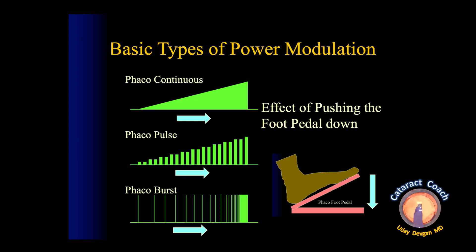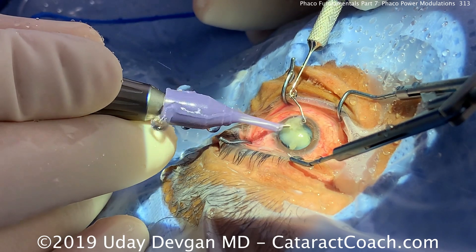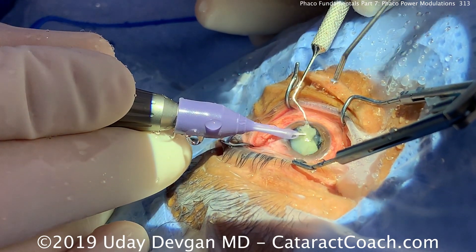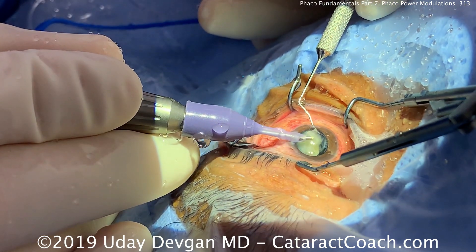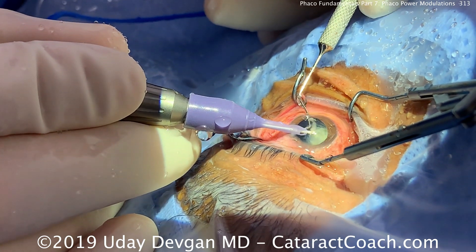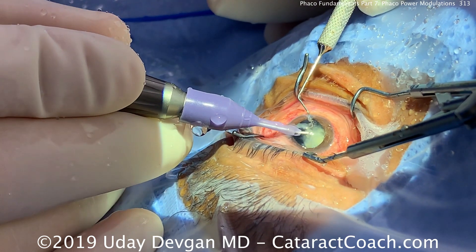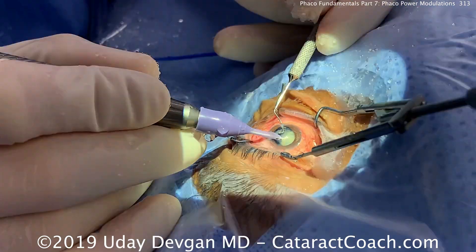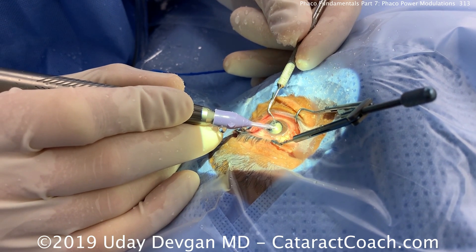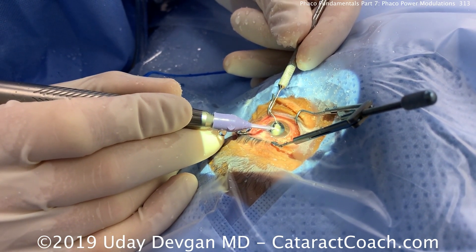The three basic types of modulation are continuous power, pulse power, and burst power. On a graph showing the effect of pressing the phaco foot pedal into position three, you can see how pulse and burst modes allow less energy into the eye and allow more cooling of the tip. In a live phaco case, the phaco tip is occluded with lens material, ultrasound energy is applied, and the pieces are broken down and emulsified — even dense cataracts can be safely emulsified.